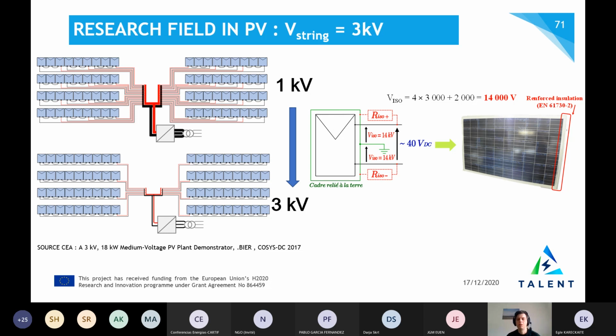So there is research work in which we reinforce the insulation of PV modules. If you take the norms, you have to withstand 4 times the maximum voltage plus 2 kV, and so you get, for example, for a 3 kV PV string, you have to insulate your module at 14 kV.